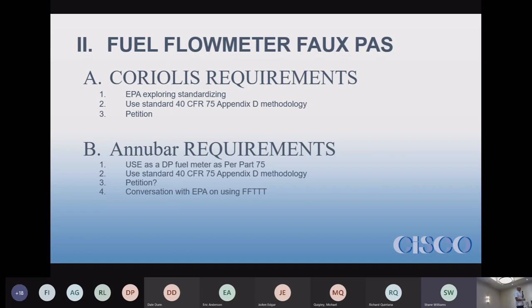The issue is right now we're in the middle of a petition, trying to get them to accept this because the principles are similar and it has the primary element component to it. But in general, if you're using something new, either use the Part 75 Appendix D normal methodology, but don't assume just because you're Part 75, the type of flow meter you have is accepted. You're welcome to call any of us at Cisco and we can walk you through it. Currently, we're in conversation with the EPA on this particular one. They've allowed us to submit technical information from the manufacturer to potentially make this similar to the work that needs. That's where we're at.